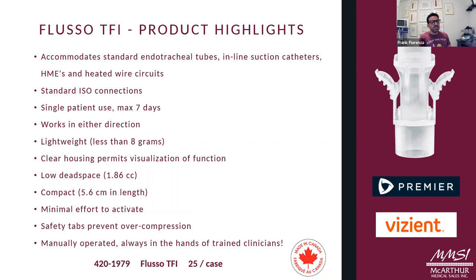It takes very minimal effort to activate. If you look at the image in the top right, you see the wings or tabs coming out with little ridges on them. You put your thumb and index finger on each tab and squeeze them together, like pinching the neck of a balloon when blowing it up. Once you squeeze those together, the device is activated, flow is occluded, and PEEP is maintained. Once you release it, everything recoils back to normal, always returning to its original shape, so we never change or increase resistance. There are tabs to prevent over-squeezing; once you squeeze it flush to where your fingers touch the device, that's fully activated, and that's the signal we look for.